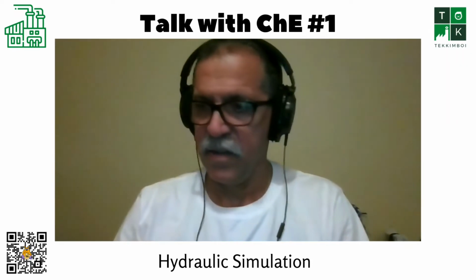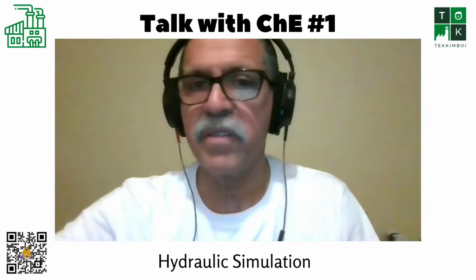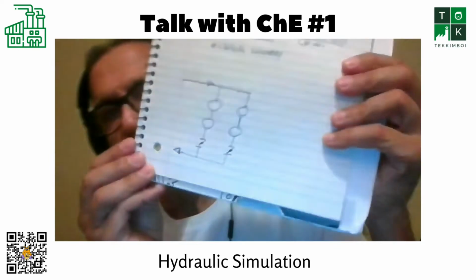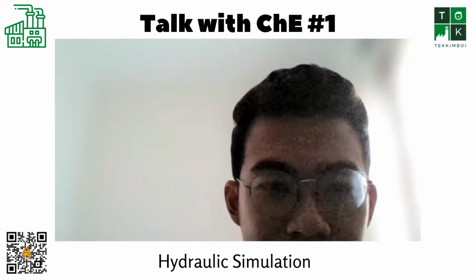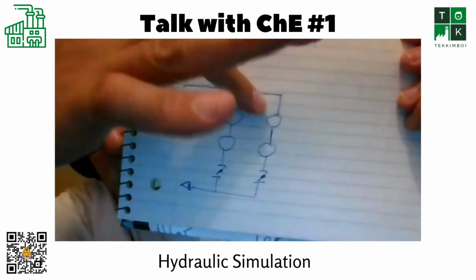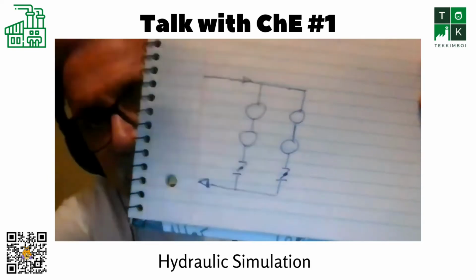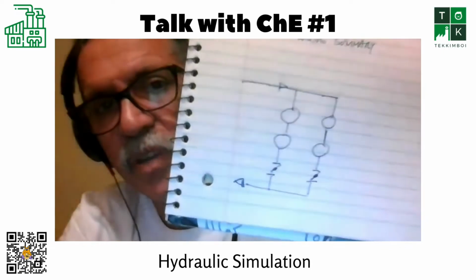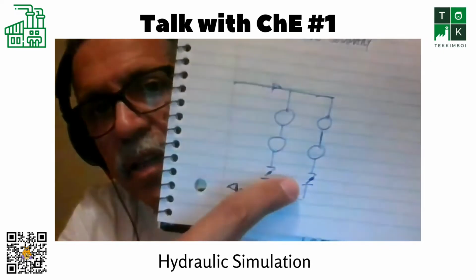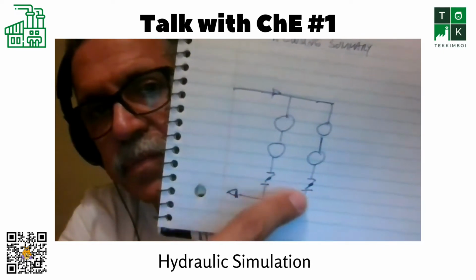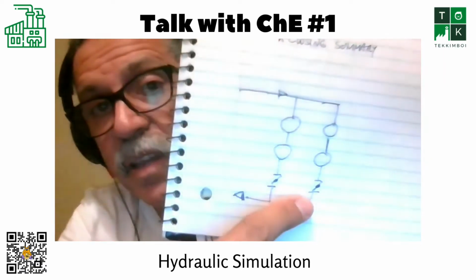They had something. The header was like this. Let me see if you can see it. Yeah, I can see. Yeah. Okay, so the water was entering like this, and then you have four condensers running in parallel, 2 and 2, and then they have butterfly valves at the outlet.